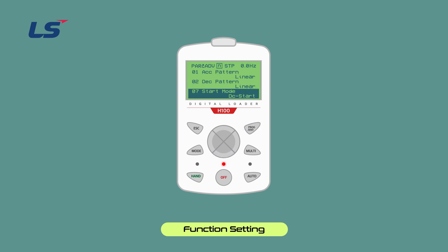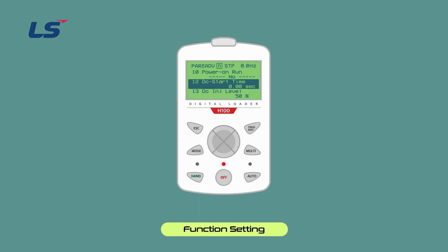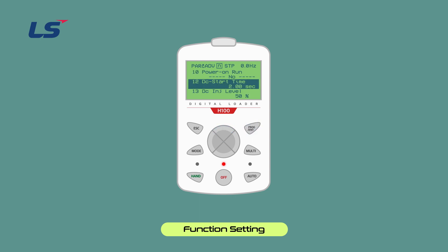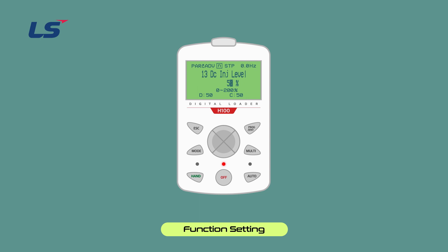When DC start is set, ADV12 DC start time and ADV13 DC injection level are activated. At ADV12 DC start time, press the Enter key and set the time using the direction keys. At ADV13 DC injection level, press the Enter key to set the DC input amount. Set the level using the direction keys and then press the Enter key to complete the setting. The direct current application amount can be set from 0 to 200% depending on the machine status.